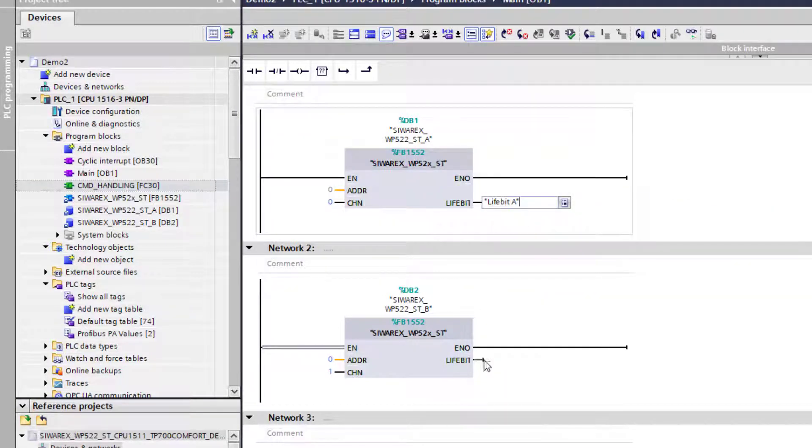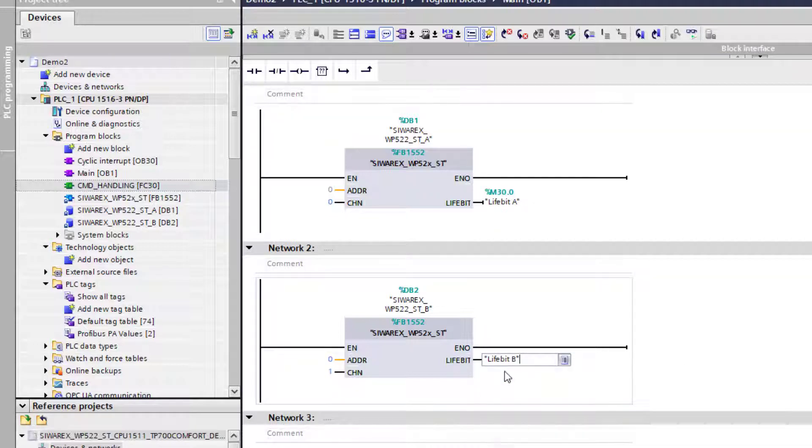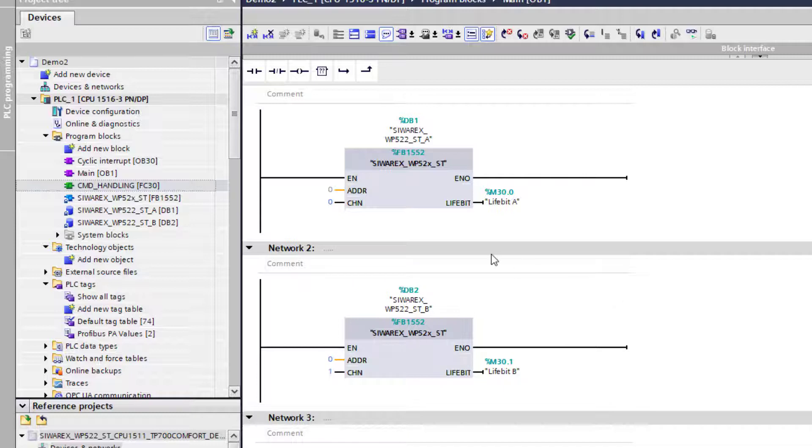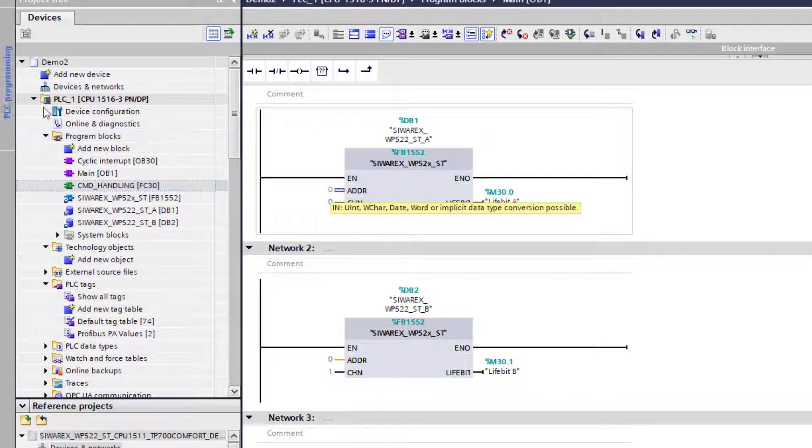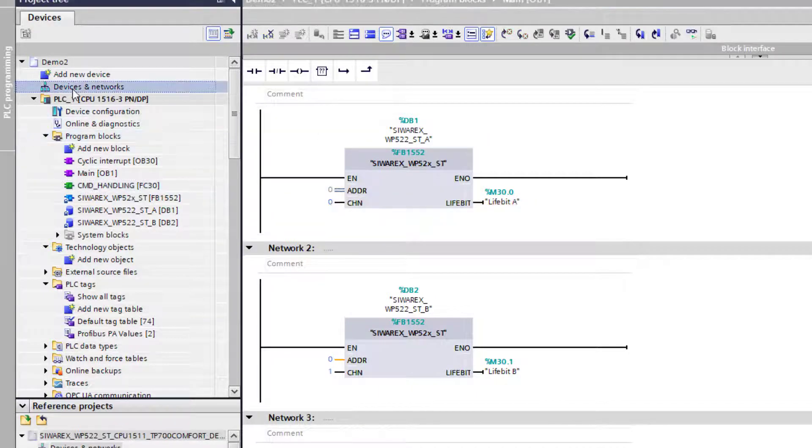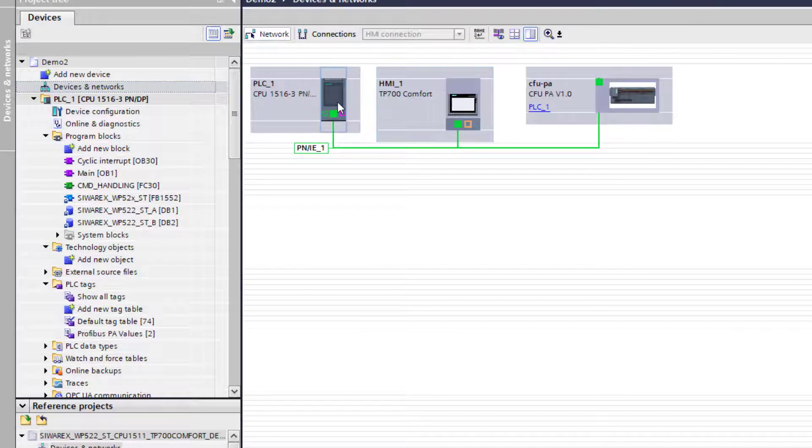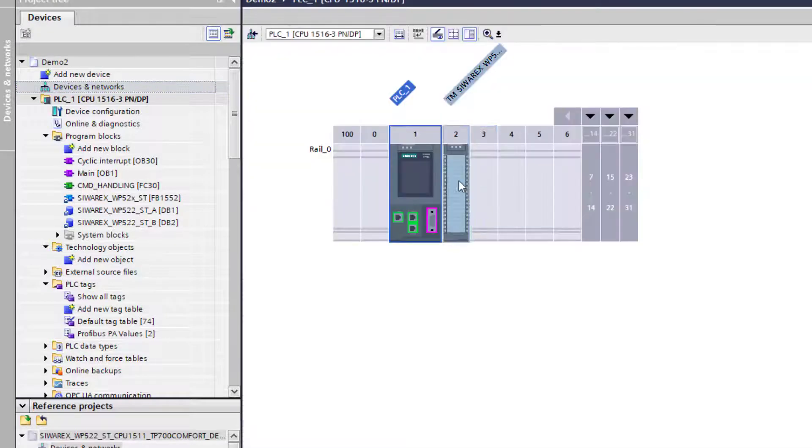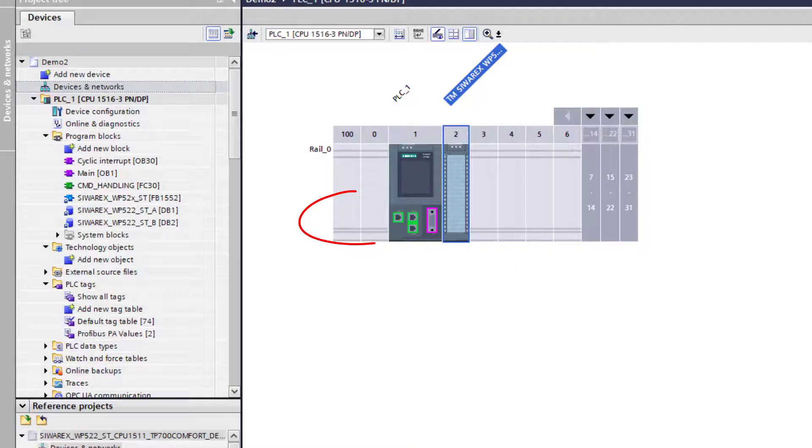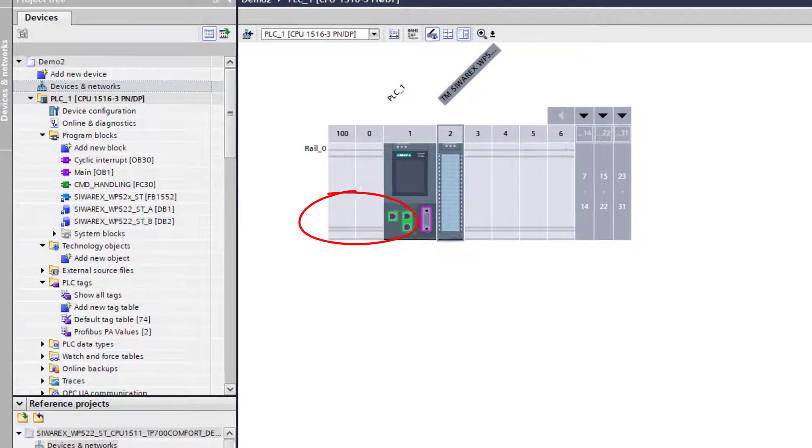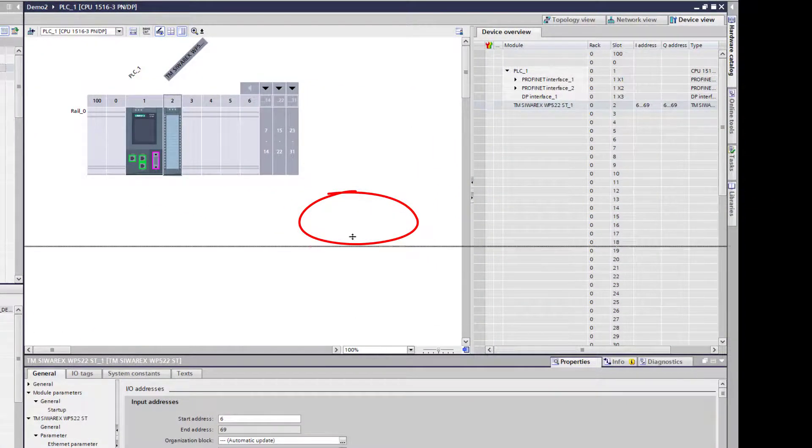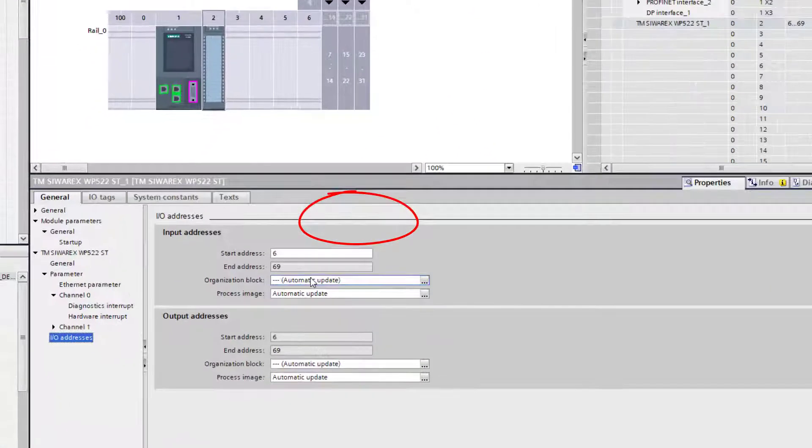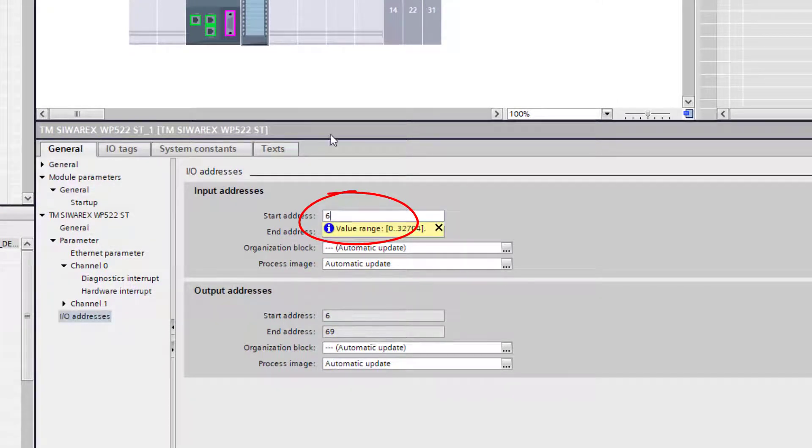We're going to put some tags in here. I've already set them up. The next thing we need to do is to find out what to put in this address here. To do that you need to go to the PLC and check the card, and what we're interested in is the start address. The start address here is six.